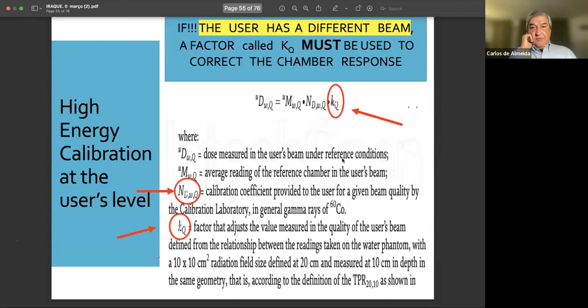But on the next slide, if you are using a different quality, like a 6 MeV beam or 10 MeV photon, 15 or 25, whatever, and your calibration coefficient is for cobalt, not for that particular energy, then you must use what we call a KQ factor. It should take into account the different response of the chamber. So to define the dose to water for this quality, which is not the Q0 of cobalt, you have to apply the calibration coefficient that was provided to you for cobalt 60, and use the KQ factor that is required to correct the chamber response. On the next slide, I'll show you what that is.